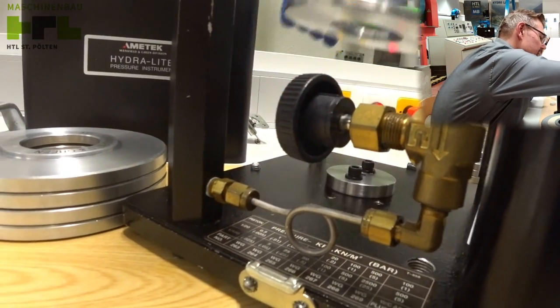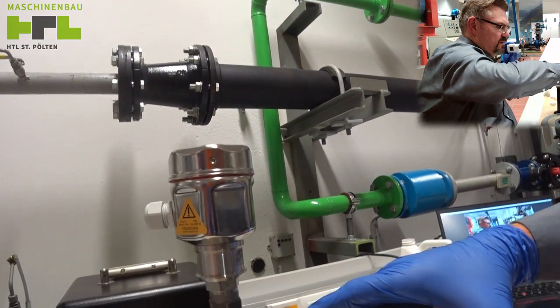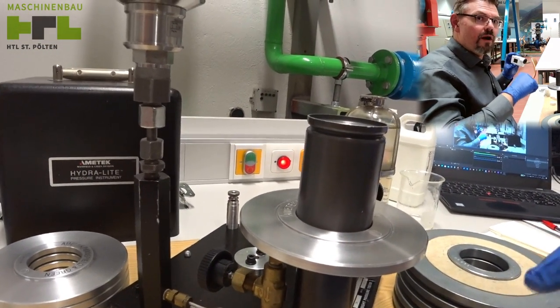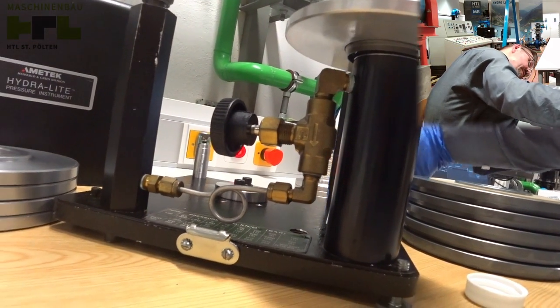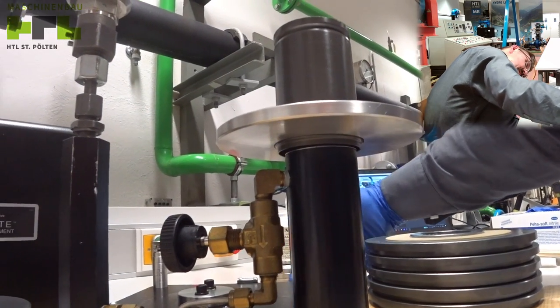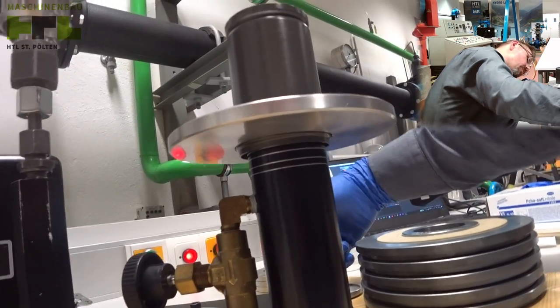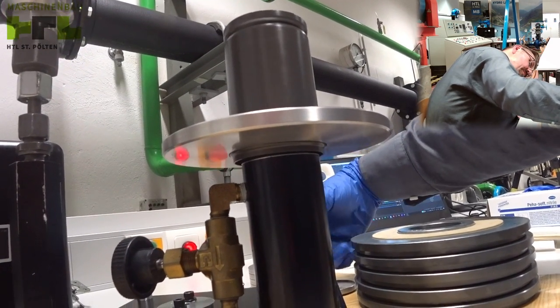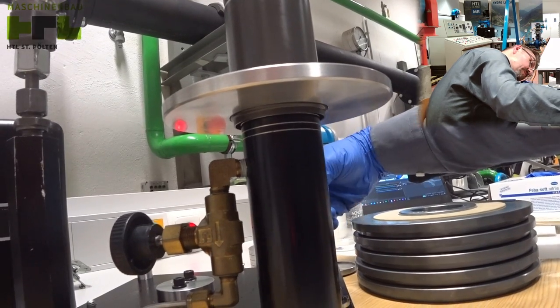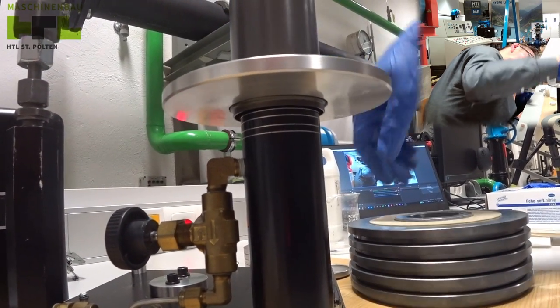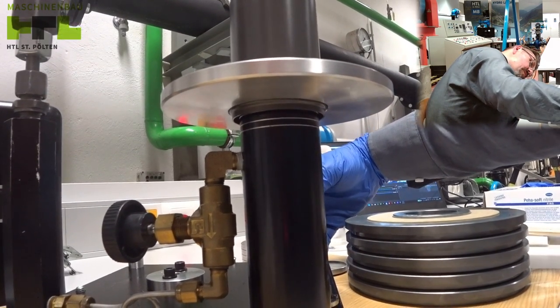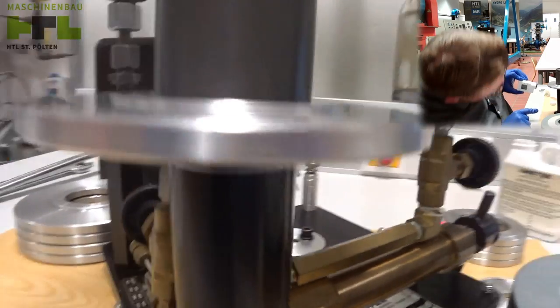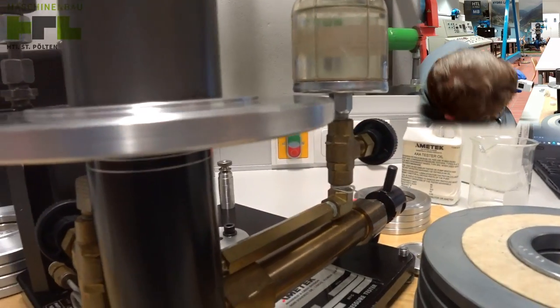So we now take this weight. This is the reference weight. With this weight on, this piston inside will have exactly one bar pressure. Let's see until it is lifted. And it should always turn, you know, it should always turn, that we are not influenced by friction.